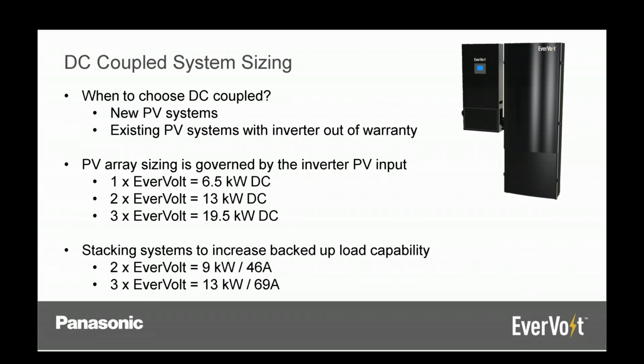Now we'll talk a little bit about DC coupled. So this is great for new systems, for existing PV systems with an inverter that might be on its last legs or out of warranty. And with DC coupled, we can have up to 6.5 kilowatts of PV DC into the inverter per inverter. So if you have a larger array than that, you can just add another inverter onto it. And then with DC coupled, we can actually stack systems now for increased backup power.